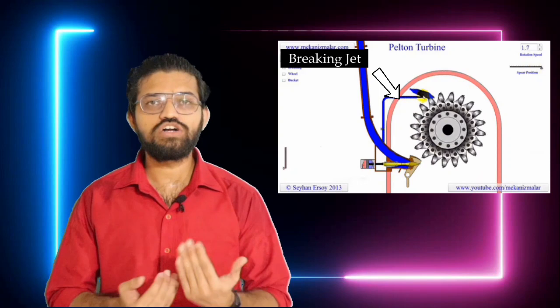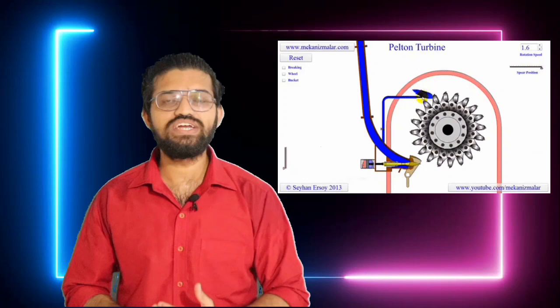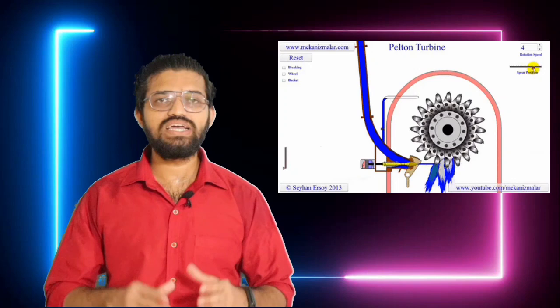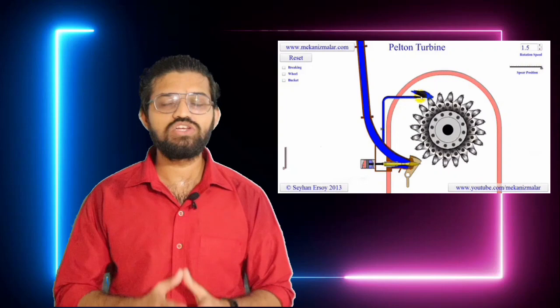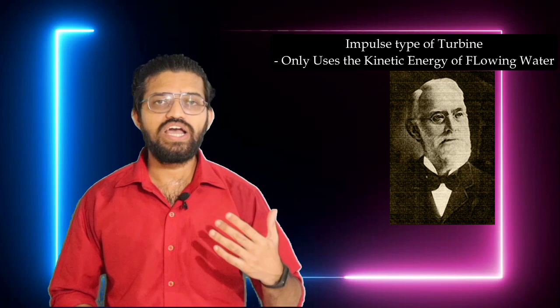To bring the Pelton wheel to rest, a braking jet is used. This braking jet is applied in the opposite direction to the bucket's motion — for example, if the Pelton wheel is moving counterclockwise, the braking jet is applied in the clockwise direction, on the opposite side of the bucket, to stop the rotation. This is the braking jet mechanism used in the Pelton wheel turbine, which is an impulse-type turbine that uses only the kinetic energy of the flowing water.